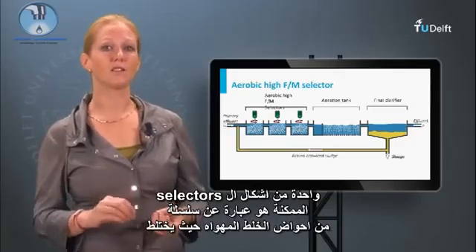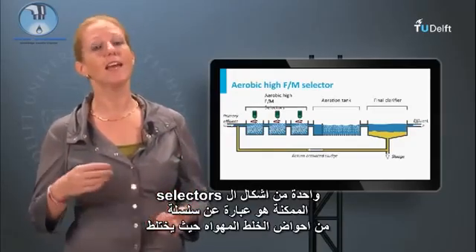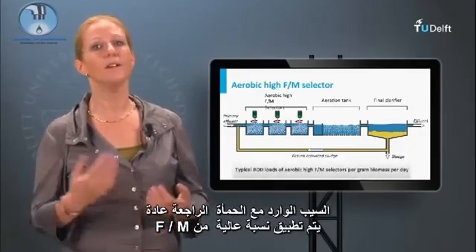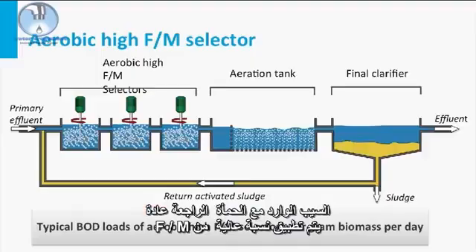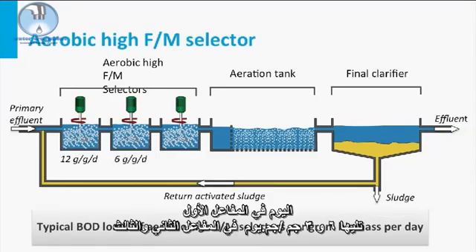One of the selectors possible is a series of aerated mixed tanks in which the influent is mixed with the return sludge. Typically, a high food-to-mass ratio is applied. BOD loads of these aerobic selectors are recommended by Jenkins as 12 grams BOD per gram of biomass per day in the first reactor, followed by 6 and 3 grams per gram per day in the second and third reactor.